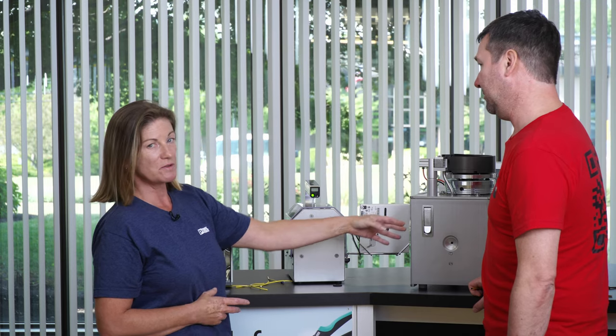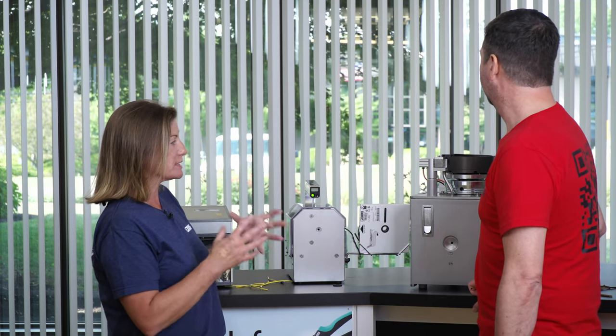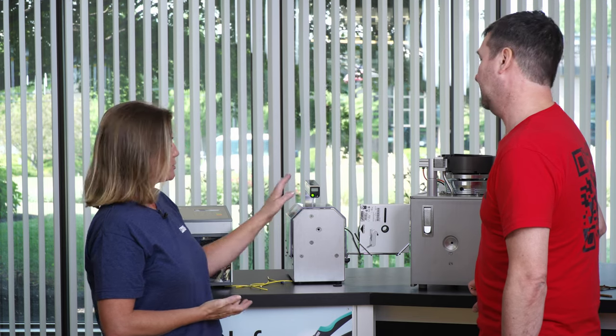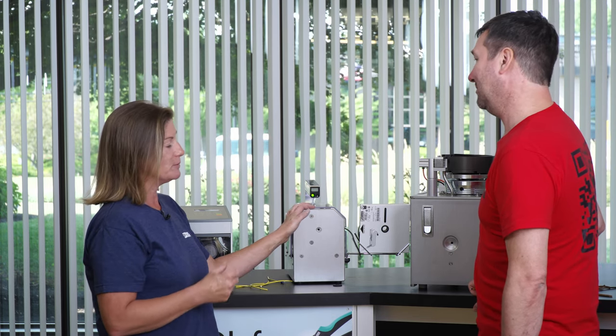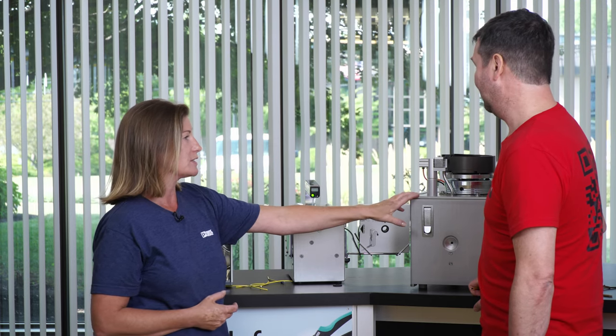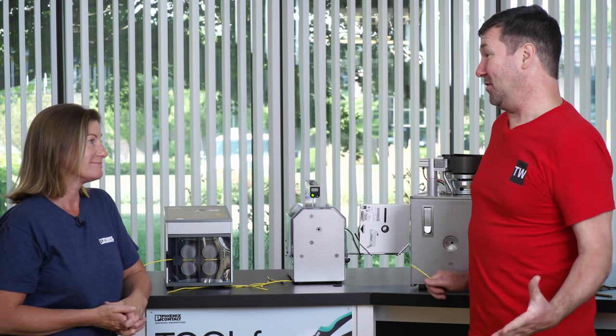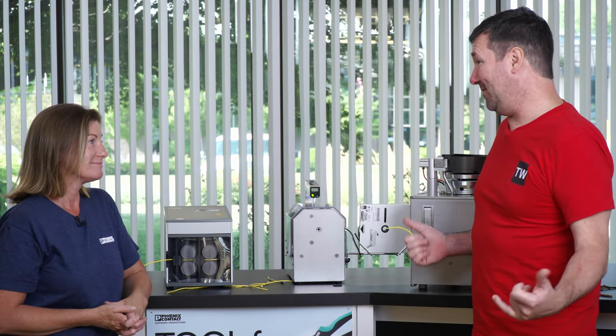The CF1000 will do a strip only, but it does strip and crimp with ferrules. Your CF3000 is limited to an eight millimeter strip length on the barrel. This guy would do six, eight, 10, and 12. What if I'm using large ferrules or I need a lug? Do you got anything for that? I do.